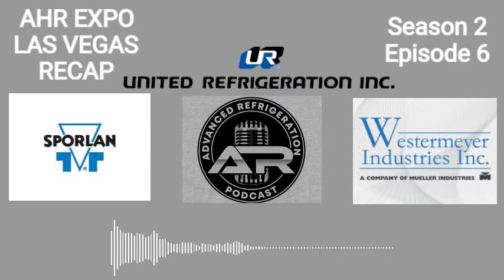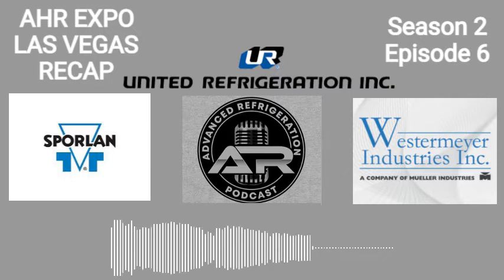Absolutely true. They're very smart valves as long as you set them up for success, but just like anything else, if you don't have the right inputs, it can't give you the right output. Absolutely. I tell my technicians all the time, you give me bad information, you're going to get a bad diagnostic. It's the same with any kind of case controller: if the suction line temperature sensor is on the liquid line, it's really not going to operate well. You're absolutely right. You have to select the right sensor, have all the right endpoints, and have the controller set to accept those.